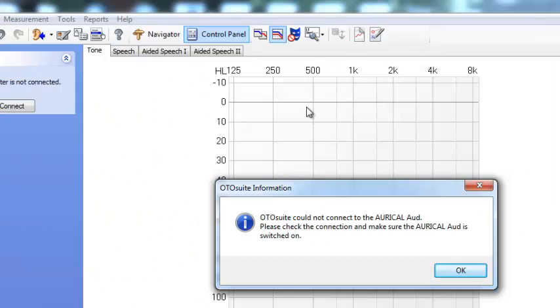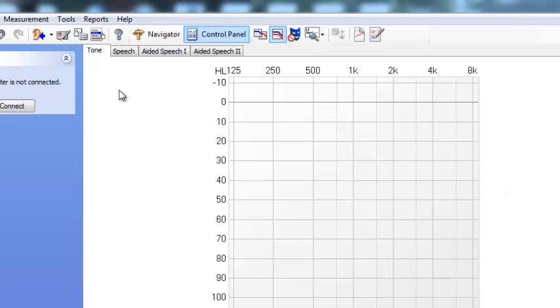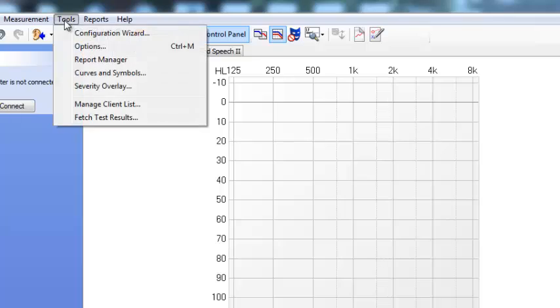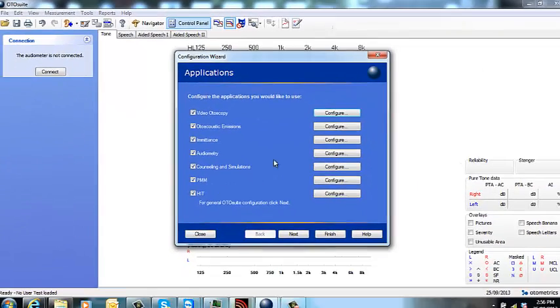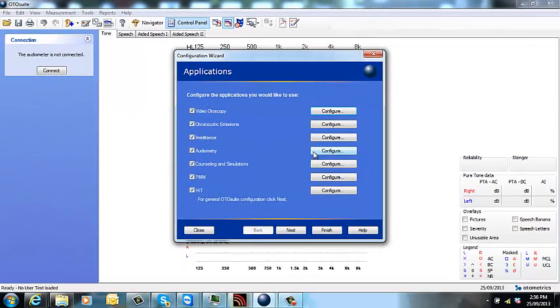You'll then get this error message which tells you that OtoSuite cannot connect to the AURICAL Aud. You just click OK and go to Tools, Configuration Wizard, Audiometry and Configure.